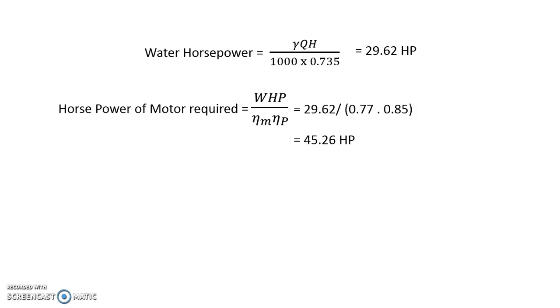Now we convert this back to the kilowatts. So how do we convert it? The power required, converting 45.26 horsepower to the nominal kilowatts, is multiply 45.26 by 0.735. This is a conversion factor. So power required is 33.26 kilowatts. So it is the equal amount of 45.26 horsepower.